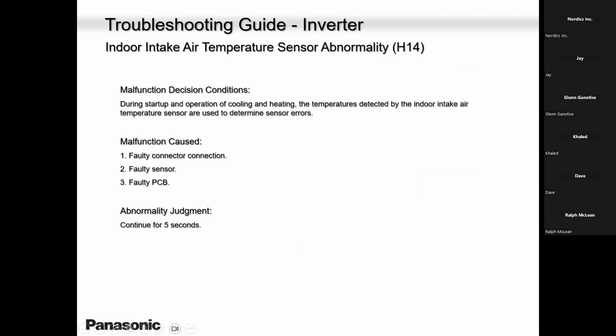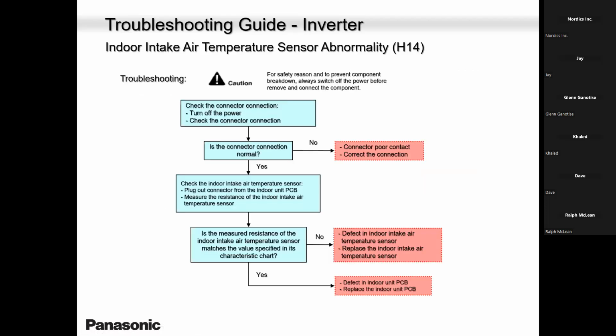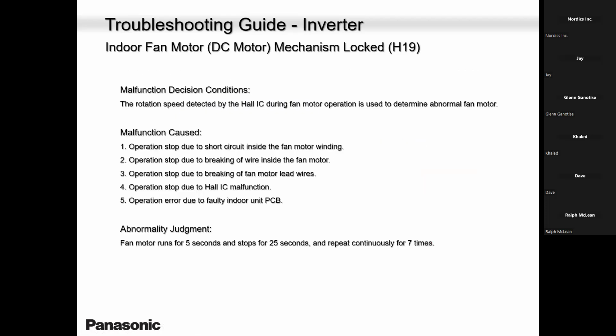So basically, we have H14 is the indoor sensor, H19 is the indoor fan motor. We do have these error codes once in a while, not much, not many. I can literally count. The ones that I can't count is the H97. It's the outdoor fan, and it happens during winter time. Most of the time when we had a heavy snowfall, the snow goes and blocks the coil. Stops the fan blade, and that's when we get the H97.